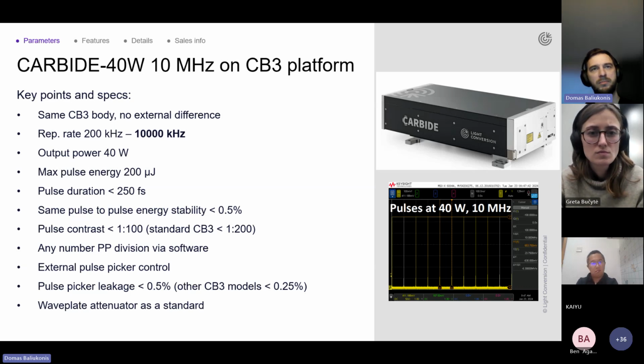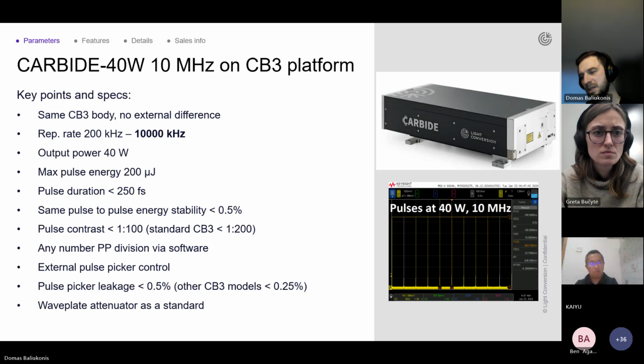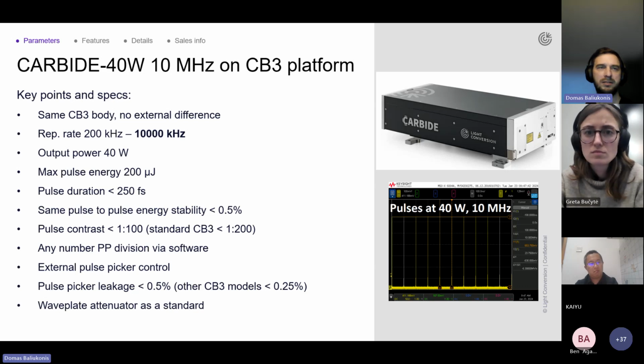What is a bit different from the standard model is the pulse contrast. Here we have 1 to 100, so we have pre and post pulses with a ratio up to 1 to 100. On our standard CB3 lasers, we have twice better this specification, but this is our initial specification, and while building more units, we are hoping to improve this parameter. But for now, for the main applications, this parameter shouldn't be an issue.